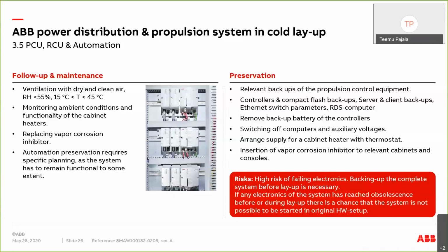But automation is electronic equipment, so humidity is important to keep in control. So vapor corrosion inhibitors need to be replaced in the cabinets frequently. For the preservation, the relevant backups have to be taken from the propulsion control system, remote control system, automation in general. There is a risk that when power is switched off, the CPUs lose their memory and they lose the last software version in the system. And to be prepared for that, we need to have backups available.